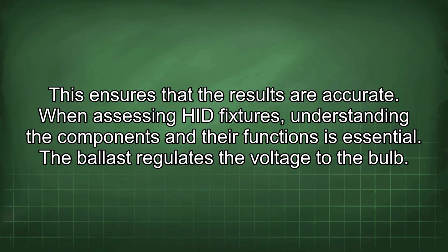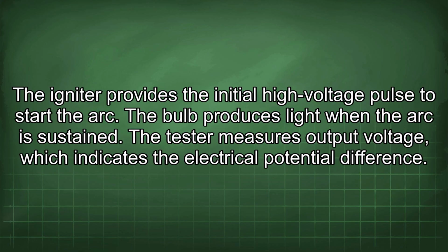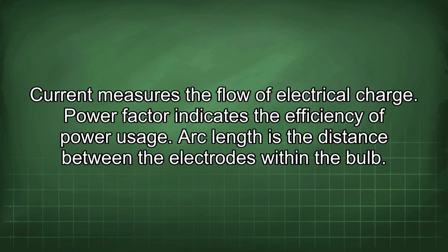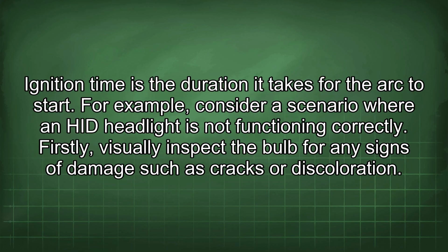When assessing HID fixtures, understanding the components and their functions is essential. The ballast regulates the voltage to the bulb. The igniter provides the initial high voltage pulse to start the arc. The bulb produces light when the arc is sustained. The tester measures output voltage, which indicates the electrical potential difference. Current measures the flow of electrical charge. Power factor indicates the efficiency of power usage. Arc length is the distance between the electrodes within the bulb. Ignition time is the duration it takes for the arc to start.